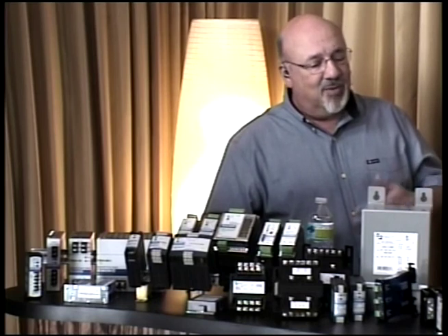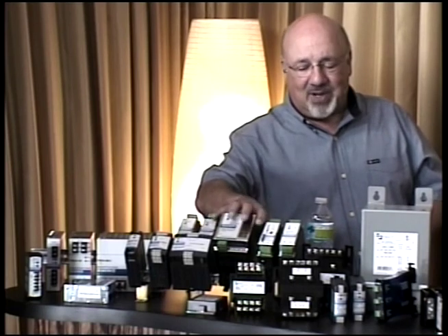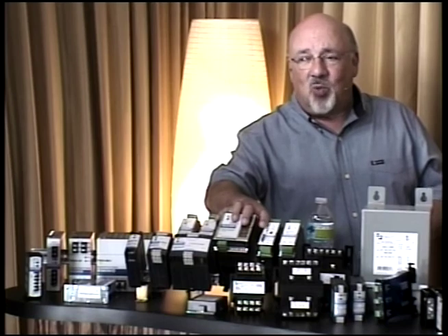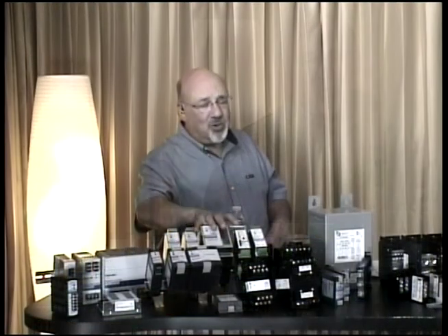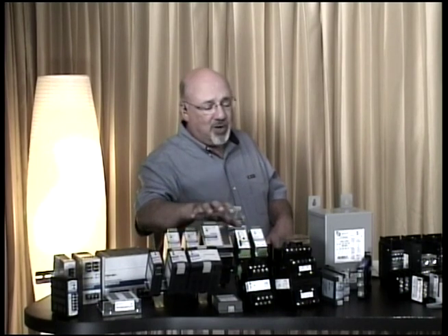And again, on stuff like solenoids and any type of inductive load, even with an unfiltered or a less filtered or regulated power supply, you're definitely going to want to add some kind of surge suppression, like a flyback diode or a blocking diode, like on a solenoid, or even a relay coil.